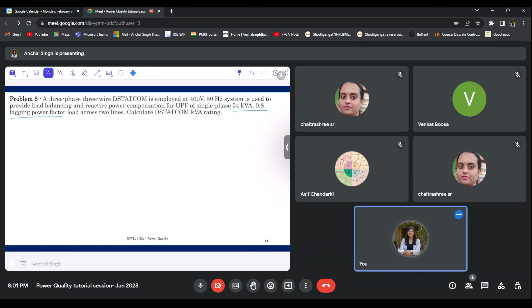So again, we have a 3-phase 3-wire D STATCOM connected to a 400 volt 50 Hz system, used to provide load balancing and reactive power compensation for unity power factor of a single phase 54 kVA 0.8 power factor lagging load, which is connected across two lines. It is the same situation which we just saw before, but initially it was a unity power factor load, and here it is a 54 kVA, 0.8 power factor lagging load. Again, you have to calculate the VA rating of the D STATCOM. The only difference here will be in the magnitude of the load currents.